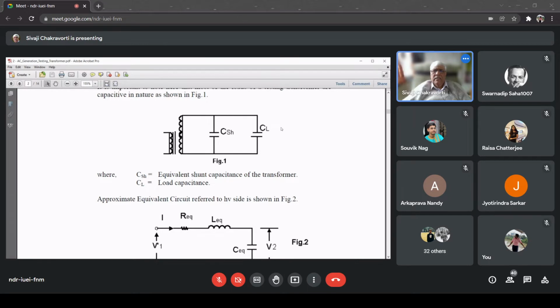very clear withstand voltage. Now, if I go by this turns ratio, then that withstand voltage will appear across the transformer terminal. But because of the negative voltage regulation, the voltage that will appear across CL will be 25% higher. So this equipment will fail in the testing in the lab. But that's not the fault of the equipment. It is the fault of our testing procedure.